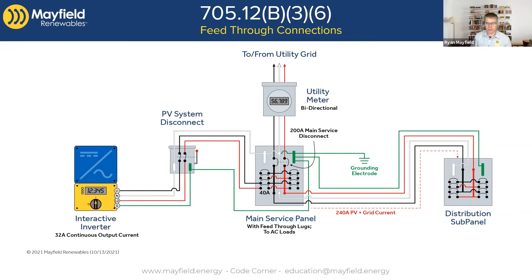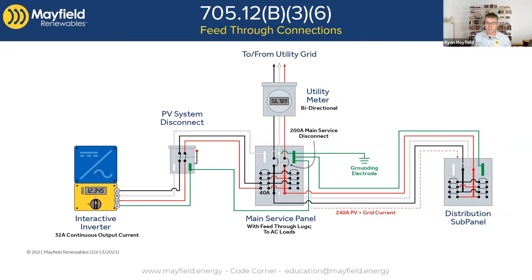As shown in the image, we would have 200 amps from the utility and 40 amps from solar, so we have a potential of 240 amps that feeder could see. We have to size the feeder appropriately. In a retrofit situation, that feeder is going to be rated at 200 amps because that's what the original installation was, and upsizing that conductor might be next to impossible or very costly.